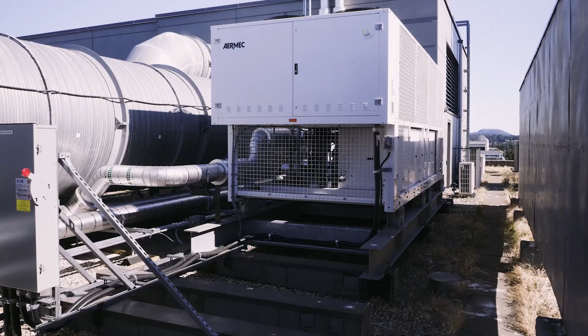So the new HVAC system at Atrium is an air source heat pump with heat recovery and an additional 250-ton air-cooled chiller. The addition of a chiller provided some much-needed redundancy to our cooling system. The air source heat pump, when we looked at the heat recovery options versus the non-heat recovery options, the energy savings and payback were just too attractive to turn down. I think the payback was around 7 years, and the energy saving component of that was very significant towards meeting our energy goals.